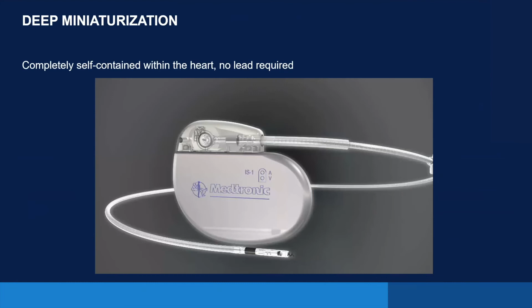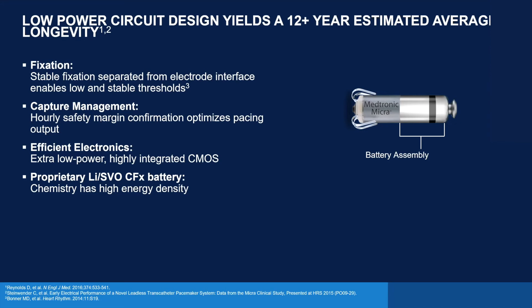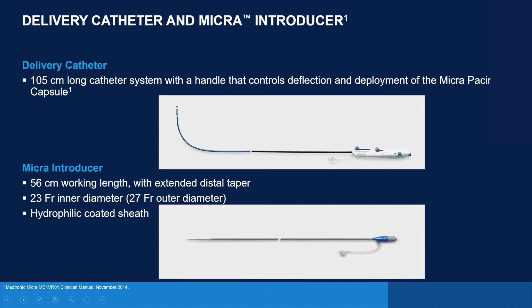Okay, so the way we fix this device within the heart is by what we call nitinol tines, which are basically like a little flexible scaffold that grabs onto the trabeculation within the cavity of the right ventricle. I won't go into too much detail, but this is basically the delivery system. There's an outer sheath. This is the 27 French sheath, which is inserted into the femoral vein. And this is the actual delivery catheter. You can see on the end of this is the Micra device. And this catheter allows us to position and deploy it in the right ventricle.